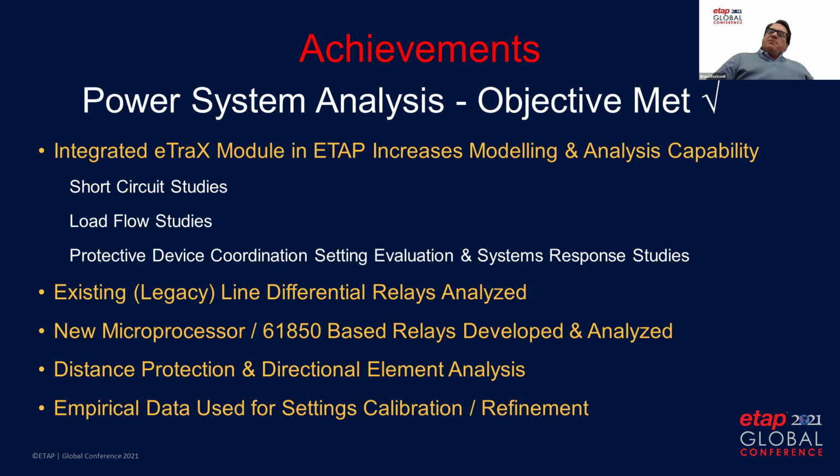ETAP imported and developed legacy line differential relays very quickly, and also inputted the new microprocessor 61850 base relays, modern technology. We evaluated and inputted distance protection elements, directional elements, and we inputted the empirical data such that we could evaluate and refine, calibrate protection settings.